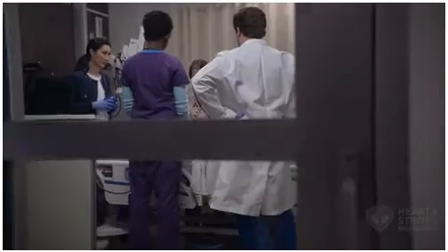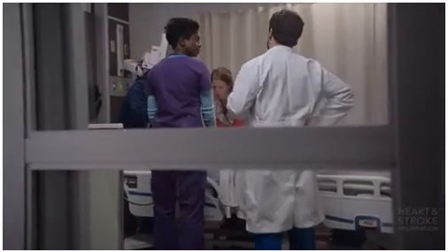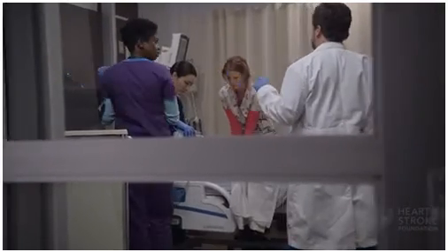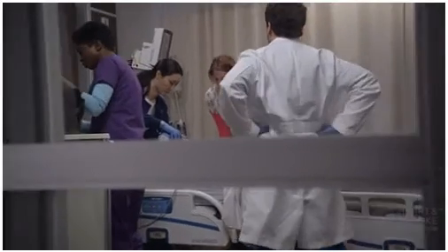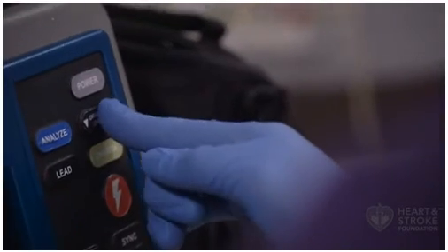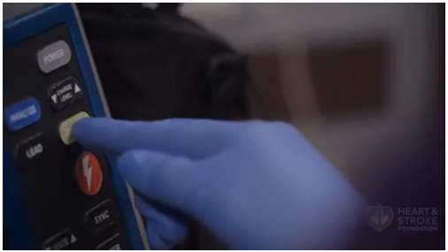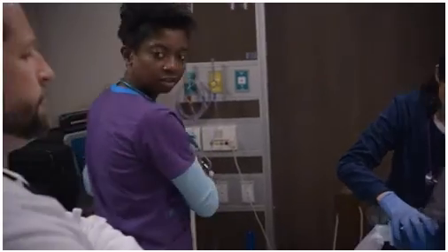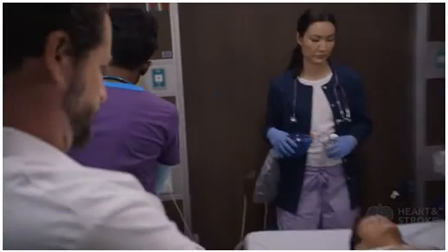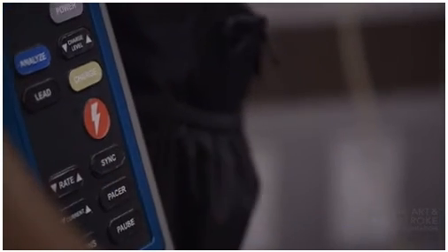A manual defibrillator is preferred to an AED because it allows adjustment of the shock dose for use on infants and children. The operation of manual defibrillators requires skill and rhythm analysis because when the manual mode is used, there is no computer rhythm analysis or prompting. The operator must determine the need for shock delivery and determine the correct shock dose.